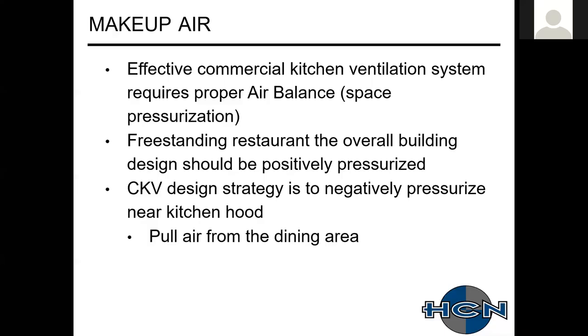A makeup air system. So the major thing here is an effective commercial kitchen ventilation system requires balance. As designers, installers, and operators of kitchen ventilation systems, you need to be the first person to call when the exhaust system isn't working. Usually you get that call of, well, my hood's not working. The hood's just a metal box.